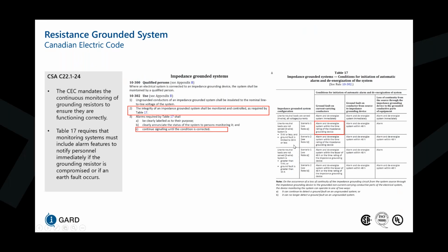In row number 2, it talks about systems that are three-phase 3-wire at 5 kV or less, and ground fault is limited to 10 amps or less. In this case, in the event of a ground fault condition, you alarm and de-energize the system within the time rating of the impedance grounding device. But if the impedance grounding device is continuous rated, then you only have to alarm the condition of the ground fault without having to trip the system. Now, when we get to systems that are greater than 5 kV, or when ground fault is limited to something greater than 10 amps, then we alarm and de-energize the system within the lesser of 48 hours or the time rating of the impedance grounding device.